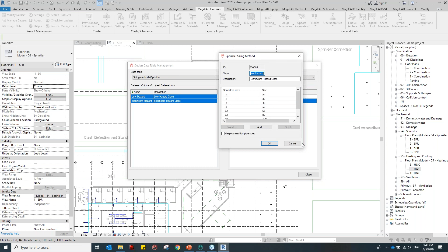Then we go for the sprinkler, MagiCAD piping, and then go for the calculations, sprinkler sizing. You just need to specify the network. For example, this whole thing is a network because it has only one open end. The first rule of thumb when you want to do sizing for the piping, whether in Revit or MagiCAD, is that there should be no open ends, not more than one.